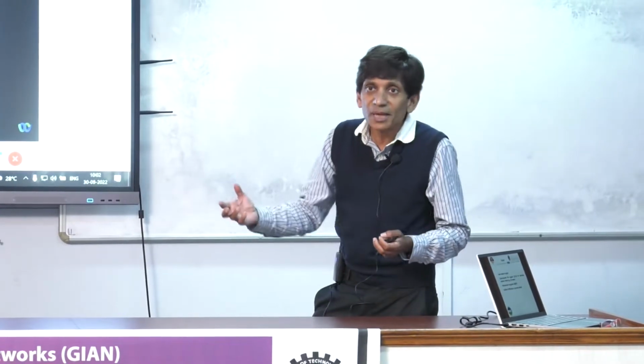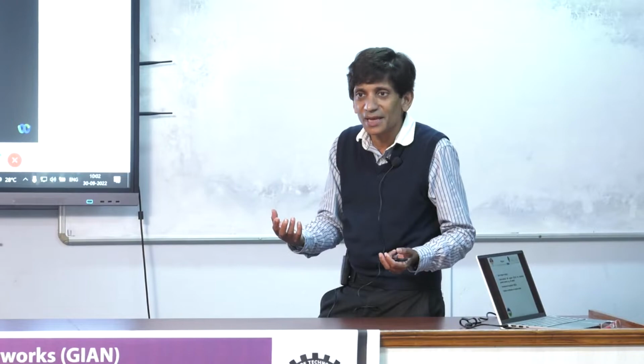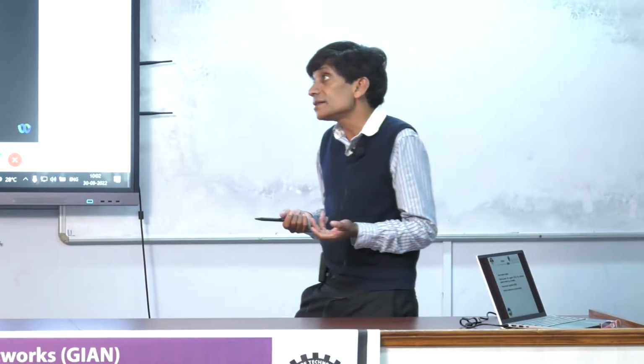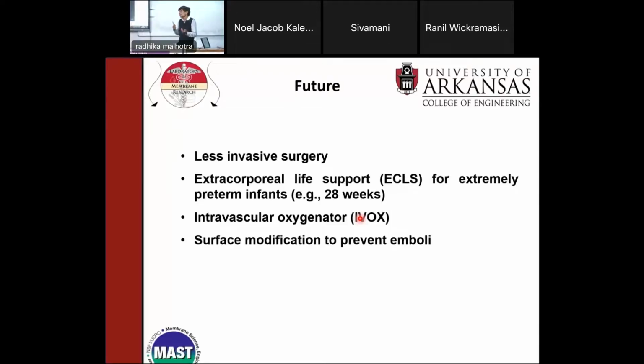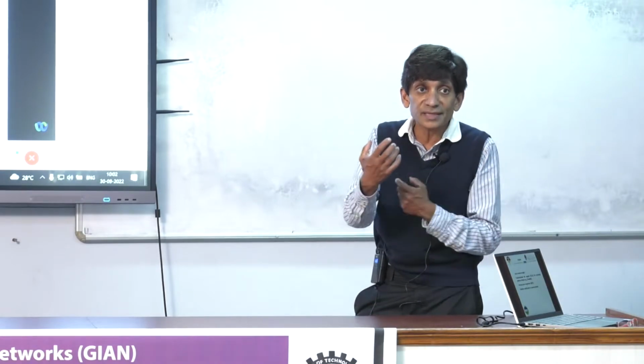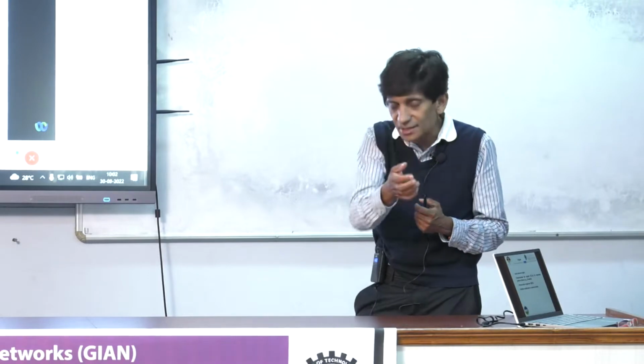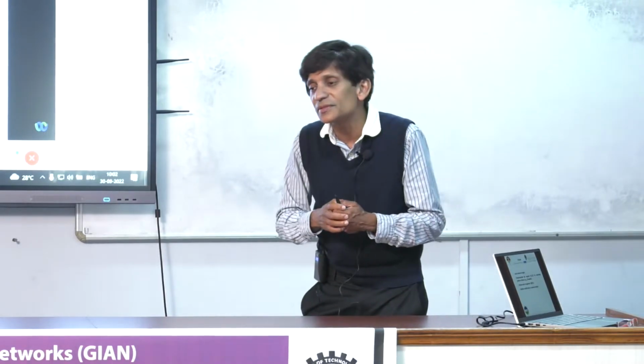Because the procedure might be okay, but how will you actually survive because of so much damage to your blood was a question. And then in the early 80s, we came up with flat sheet silicone rubber. It's a dense membrane. Now sterility is not a problem, and blood damage is not a problem. The problem is you don't have good removal of CO2. So gas exchange rates are a problem. There's good passage of oxygen into the blood, but not good removal of CO2.